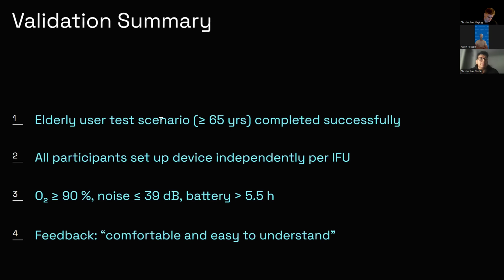So here's our validation summary. We validated the Rove 6 with its intended users, which are elderly adults of 65 and older. Each participant independently assembled and operated the device using the instructions for use without any assistance. The metric results match our engineering specs, more specifically oxygen purity of greater than or equal to 90%, noise levels of less than or equal to 39 decibels, and battery of greater than 5.5 hours. Feedback described the device as comfortable and easy to understand. That confirms that the design not only meets the specification, but also fulfills its intended use and usability requirements for home and ambulatory therapy. Next slide.